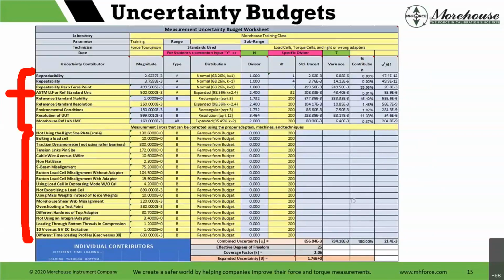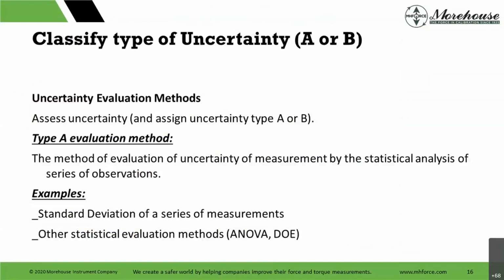However, if someone's sending us this from, let's say, California, they've unbolted a load cell, they've sent us instructions: hey, use the star pattern and bolt to 8 pound-feet of torque, right? But is it the same screws, the same base? You get into a lot of different things. So there's a lot of traction dynamometers, pin, S-beam misalignment. There's all kinds of stuff in our uncertainty course if anybody ever decides to take that, where we talk about all this stuff. So classify the type of uncertainty, A or B.